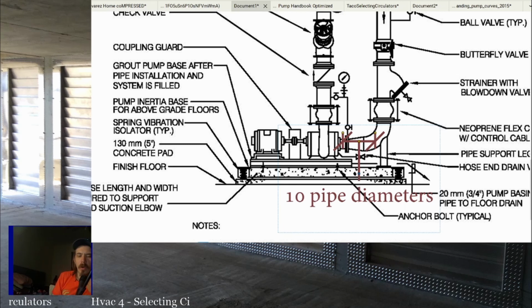And again, even on the smallest, I think they're like 002s or 003s or something, that they use on circulating lines for hot water, for domestic water. Even on those, where they have a 90 going straight into the pump, I've seen those pumps cavitate like crazy. You can just hear the pump cavitating, but it's such a small circulator, people think the noise is normal because it's not quite as gravelly as the bigger pumps get. All right. But even on an inline circulator, you can cavitate if you've got a 90 right before the pump. So 10 pipe diameters on the suction side of a pump is important.